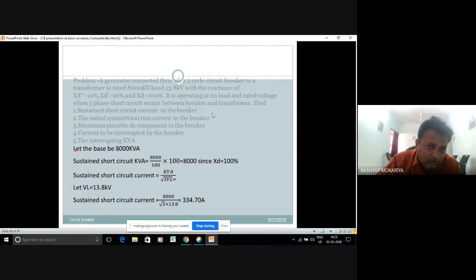That was a query from one of my friends from GEV. You can see the subtransient reactance X_d'' is 10%, transient 16%, and X_d is equal to 100%. A generator connected through a 5-cycle circuit breaker to a transformer is rated 8000 kVA and 13.8 kV. Then find the sustained short circuit current in the breaker, the initial symmetrical RMS current, the maximum possible DC component in the breaker, the current to be interrupted by the breaker, and the interrupting kVA.